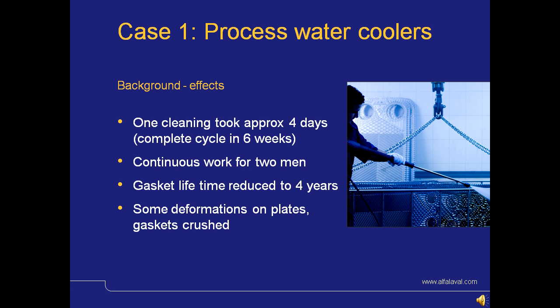And another side effect, apart from this being a time-consuming and a difficult job, was that the gasket lifetime was reduced to 4 years, out of perhaps 8 that it should have lasted, or 10 maybe even. There were some deformations on plates and gaskets crushing as a result of frequent opening as well. As you may know, every time you open a heat exchanger, there is a risk of something happening while closing it again.